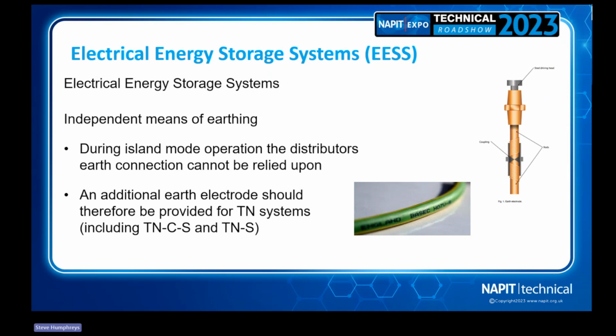So for those that remember the days of doing diesel generators, you used to have them a lot at supermarkets or MOD places. If you put one of those in and you've got a UPS system that runs in between that generator kicking in, you used to have to spike them, because if you think about it, if it's gone into island mode, the regulations tell us that we cannot now rely on the distributor's earth connection. It may still be there, but we cannot rely on it. So we took our training rig out recently to a few shows, and people see our earth electrode on our training rig and say, that's TT. It's not TT. When it goes into island mode, it's TN-S. And there's a diagram in a bit that shows that.